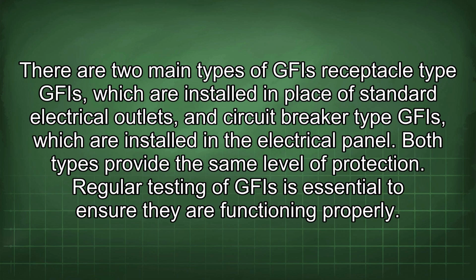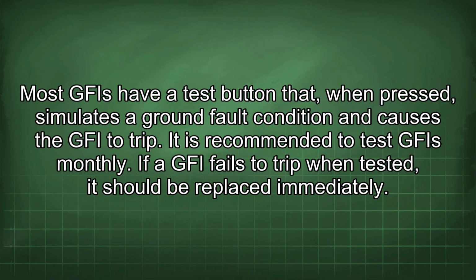Regular testing of GFI is essential to ensure they are functioning properly. Most GFI have a test button that, when pressed, simulates a ground fault condition and causes the GFI to trip. It is recommended to test GFI monthly. If a GFI fails to trip when tested, it should be replaced immediately.